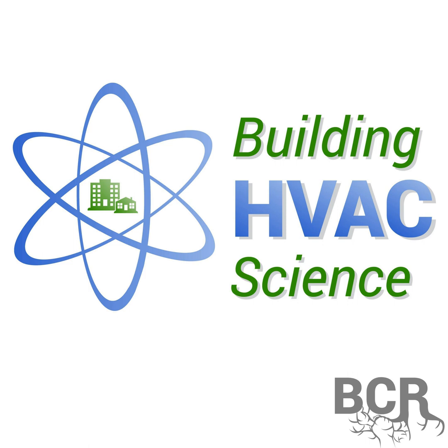So we start off with really tight ductwork, and we start off with high MERV filters. So MERV 13 is the starting point. If you ask a lot of indoor air quality researchers what's the starting place for good filtration, they'll usually say MERV 11 to MERV 13 or something along those lines. So we use MERV 13 filtration as our standard. And then we make sure that all of the air that's moving through the ductwork is moving through the filter. So that's really the first step, is to use that really good filter.